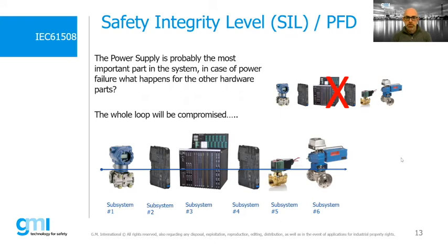The main concept that needs to be understood is that every single element of the system must be sized with a SIL level, such as to allow us to obtain the overall SIL of the system required. All the power supplies that are part of the SIS, for example those that power the PLC-DCS, those that supply voltage to operate valves and actuators, and those that allow barriers, isolators and transmitters to work properly, also follow this fundamental rule in a safety-related loop. It's important that they also have an adequate SIL level. All components of a SIS, including power supplies, must be safety related and have a SIL level. This helps us to have a safety loop, and with the correct redundancy, a loop with high availability to the process.